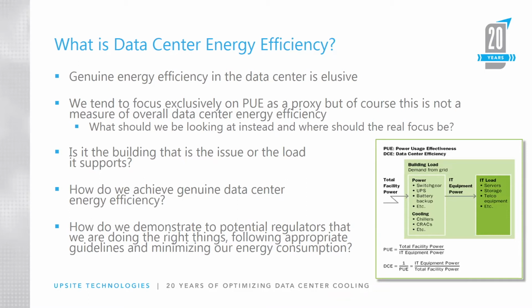If you've got no IT load, the building doesn't consume any energy. The building merely puts a slight overhead, or it should be a slight overhead, on the energy consumed by the IT load. And that is effectively PUE.